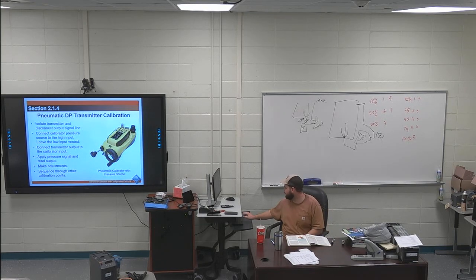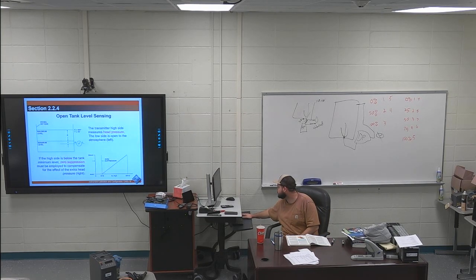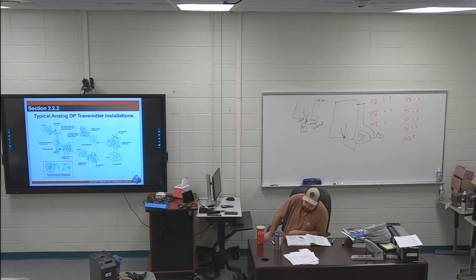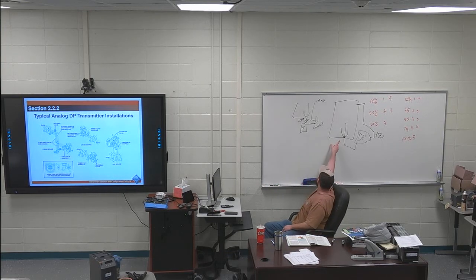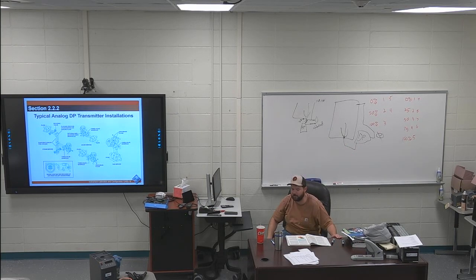Head pressure, 223. First sentence of 223 is highlighted. Differential pressure transmitters used for liquid level applications measure static pressure, commonly called head pressure. Is that what that is? The pressure meter, yes. But that's also what the one you're going to do in the lab is. I mean, that's why I talked about head pressure is pushing onto your high side of your transmitter.